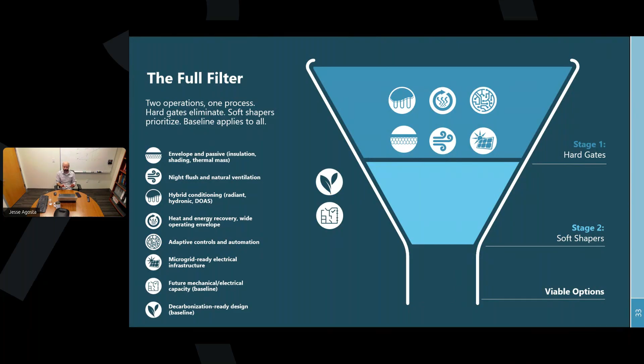Let's look at our first stage, the hard gates: climate zone, occupancy, and code. Starting with climate zone—it certainly needs to be taken into account to choose the right system. It won't eliminate or impact everything, but what it does impact, it impacts a great deal. For example, night flush and natural ventilation work really well in a temperate climate with medium cool temperatures at night. If it gets down to about 15 degrees, that's too cold. If it stays above 85 degrees with high humidity, night flush won't be effective. So climate can pull out a system or amplify another to keep it in.